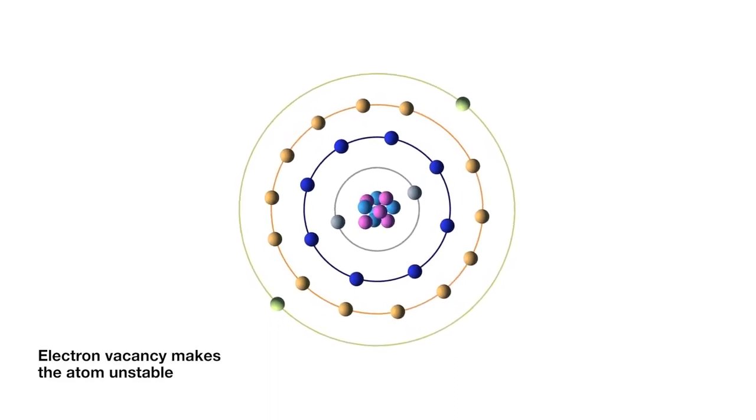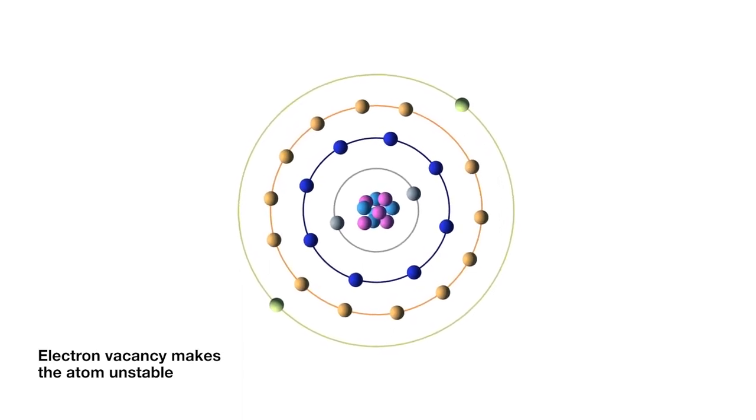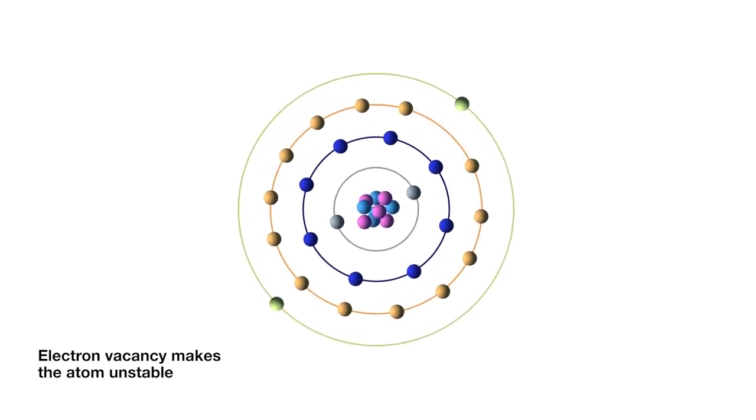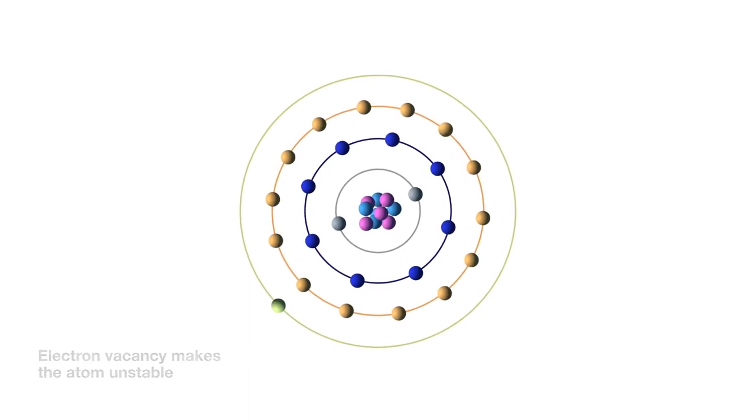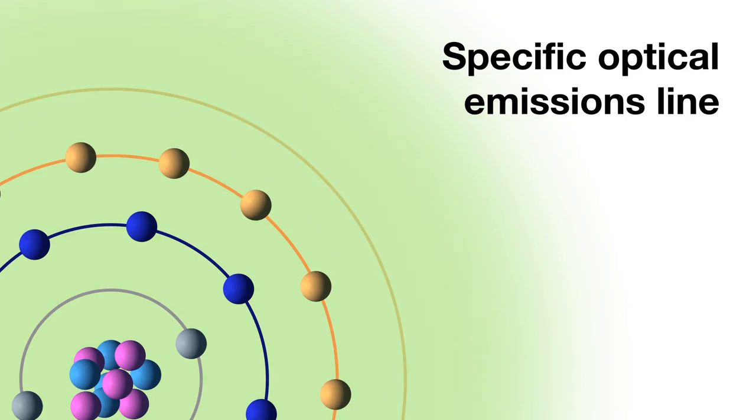The ejected electrons create a vacancy, making the atom unstable. To restore stability, electrons from higher orbits further away from the nucleus drop down to fill the vacancy. The excess energy released as the electrons move between the two energy levels or shells is emitted in the form of element-specific light or optical emission. Every element emits a series of spectral lines corresponding to the different electrons' transitions between the different energy levels or shells. Each transition produces a specific optical emission line with a fixed wavelength or energy of radiation.